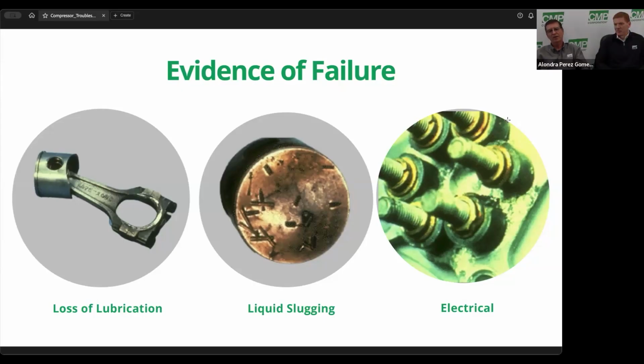And while we're talking about electrical problems, and we've been talking about semi-hermetic compressors, if you have a scroll compressor that's 3-phase, and I did it on my church 3 months ago, if you run a scroll compressor backwards, it's going to sound like it's going to blow up. Yeah, it sounds like marbles. And there's nothing wrong with the compressor. You just got it running backwards. So the scroll compressors, if they run backwards on 3-phase, it lets you know it. I could not turn it off fast enough. I knew what I was doing, I thought, but I just crisscrossed one wire or two wires there and caused it.